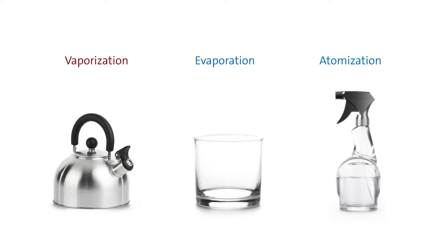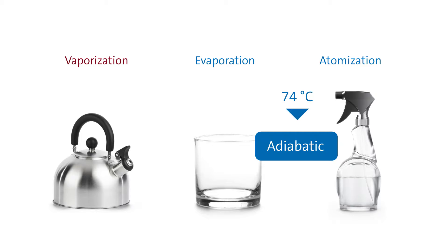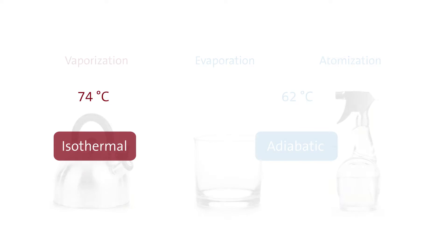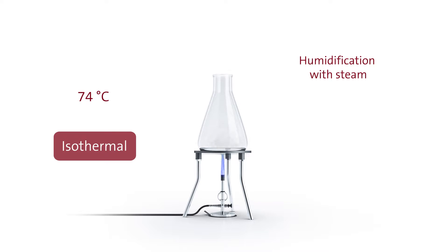The essential difference between these methods lies in the fact that with adiabatic methods air is cooled down. However, the air temperature remains constant with steam humidification. Steam does not require additional energy to enter into gaseous state since it already is gaseous.